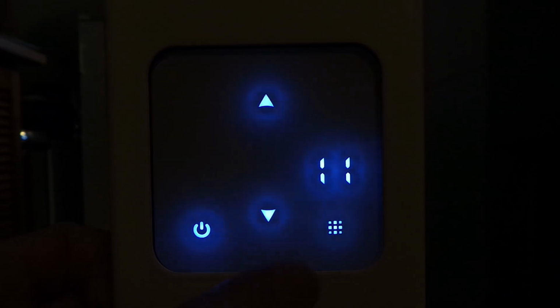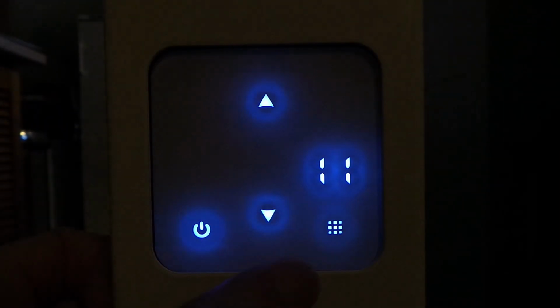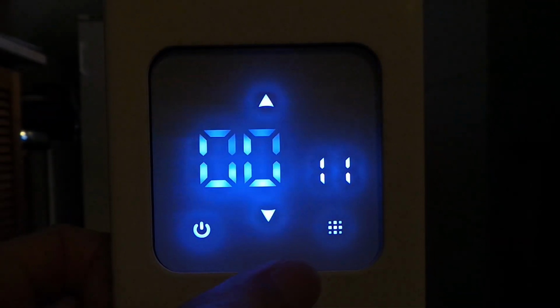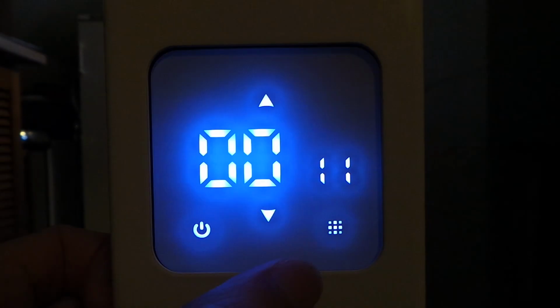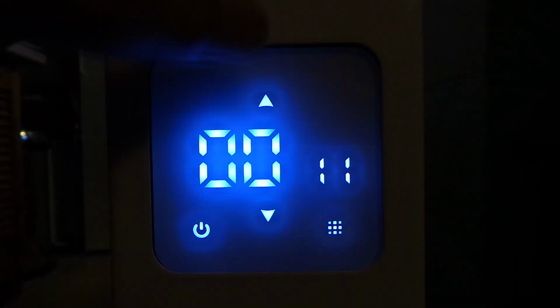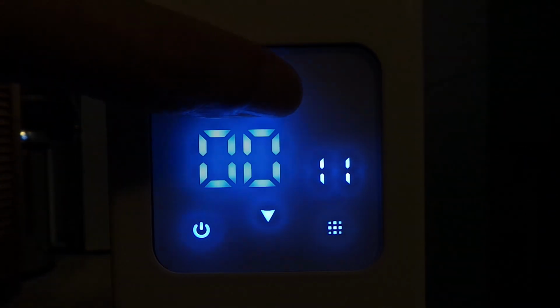And if you're in this default state of 0, then when you do the programming for the thermostat times that it comes on, it allows you to set certain program values, times and thermostat settings for 5 days, which will be the same, and then 2 other days, which are days 6 and 7, will be different. That's useful if you want to have different programming for the weekend.